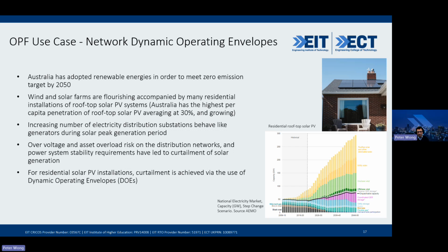As a matter of fact, we believe that right now, when we add all these renewable generations together in capacity terms, they already are bigger than what is available through the central power stations, and into the future they are going to occupy a very high percentage. With the increasing number of solar systems on the rooftop, a lot of our distribution substations, the substations that convert the medium voltage, for example 22 kV, into 400 volt to supply the customer, are behaving like generators now during the solar peak generation period.